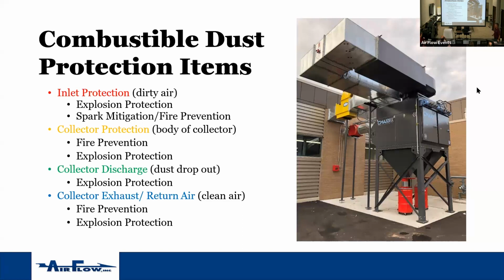And you'll have your explosion protection. On your discharge, discharge is down at the bottom. You'll have explosion protection. We don't have to deal with fire prevention in here unless you're enclosing this and running some type of conveyor or a screw conveyor of some type that's taking the dust to a different collection point. And then on your return air side, you'll have your fire prevention and you'll have your explosion protection.